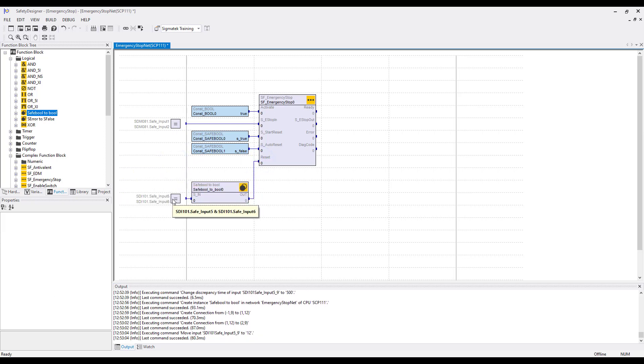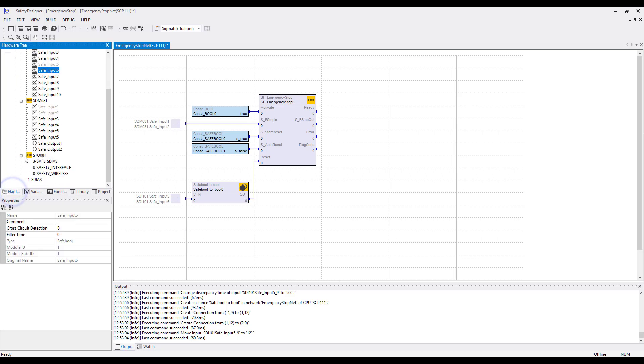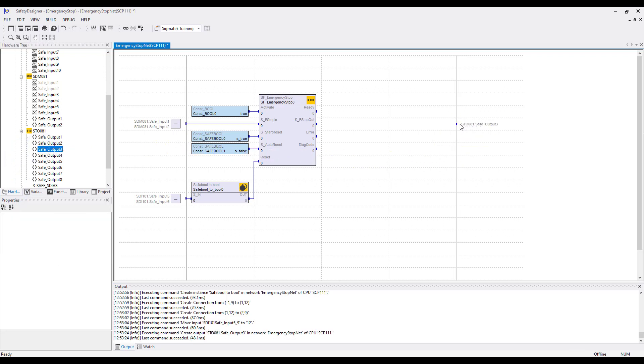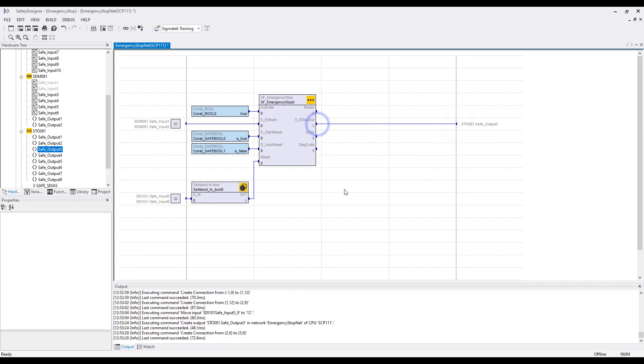To switch off the green light when there is an emergency stop, go to the hardware tree and take from the STO081 the safe output 3. Drag this to the output side and connect safe output 3 to the Emergency Stop Out. To delete unused columns, right-click on the column and choose Delete Column.